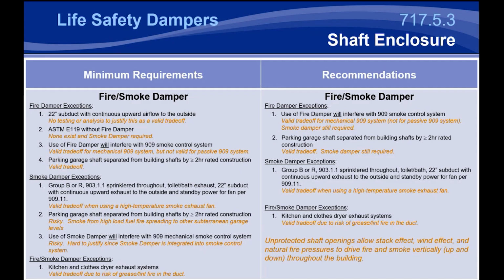Now, if you've got a parking garage that's separated from a building with more than 2 hour rated construction, you can certainly remove the damper requirement for that. Most of your above ground parking garages that you see are going to be naturally ventilated. Where this can be a bit risky is when you're dealing with subterranean parking garages that do have to have ventilation, because there is the potential for a high fuel load that is between your occupants and any means of egress. If you've got people below the fire and they have to get past that fire, it could be a dangerous situation where they actually have to move past that fire, past the smoke, to be able to get out of that subterranean parking garage if there is a fire.